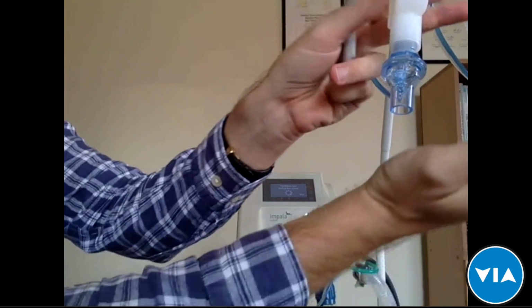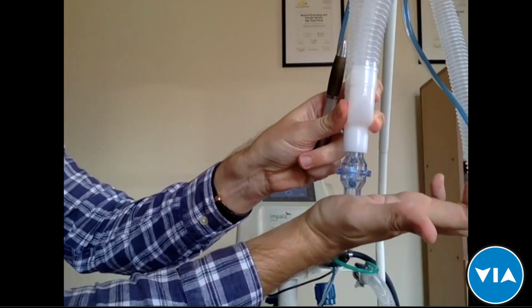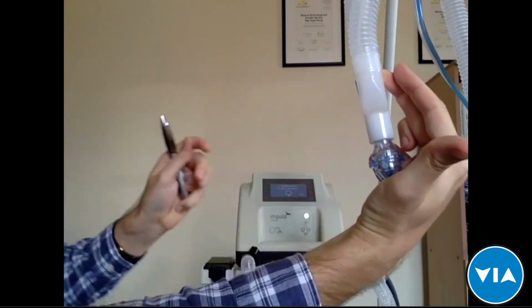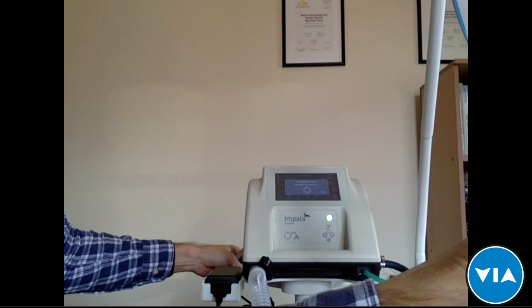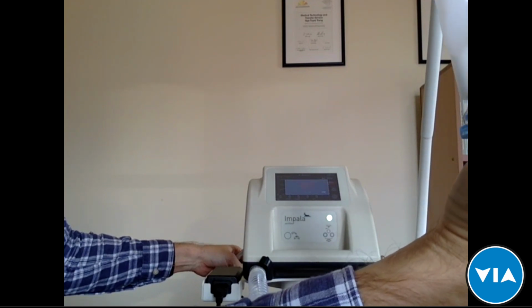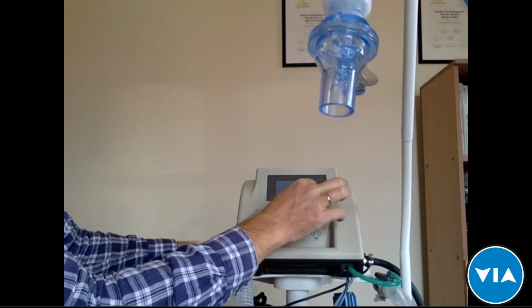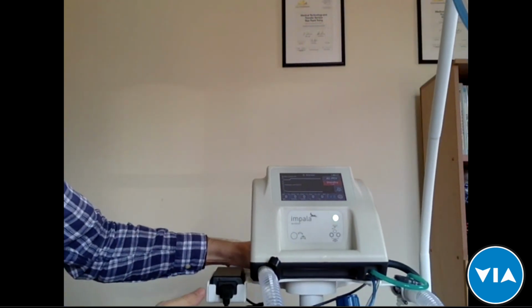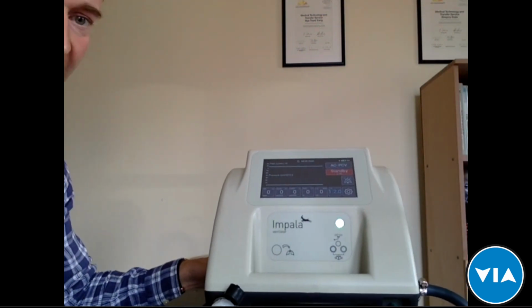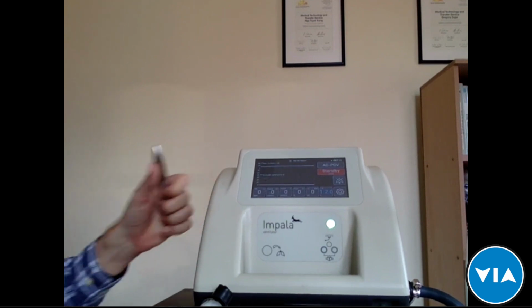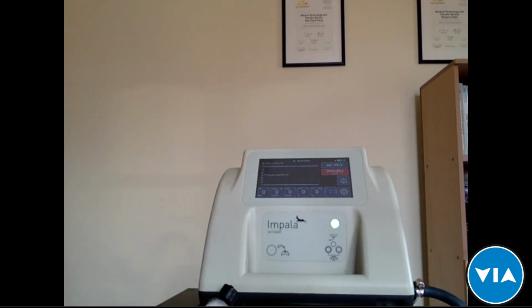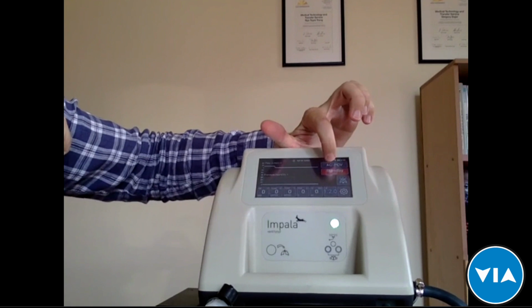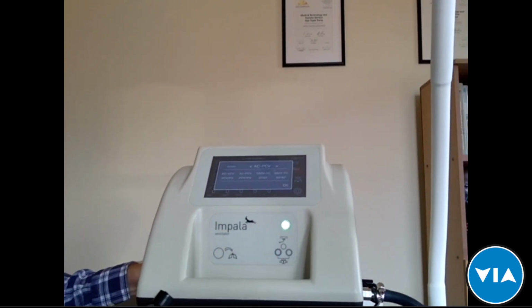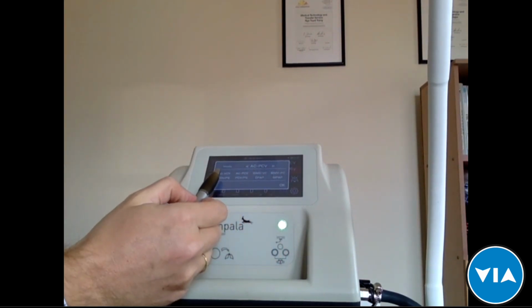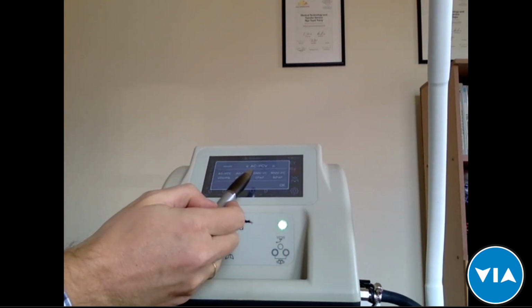And the last step is what's called the occluding test. So we have to put our hand, block the outlet to make sure that the device performs the final calibration step. I failed that, I didn't occlude it, but it's okay. We can skip all those tests to go directly to operation mode. And now we are in operating mode. I connected back the test lungs, which is off the screen, so we can see how the device works. The device has many modes, as many ventilators have, and those modes are volume controlled and pressure controlled.